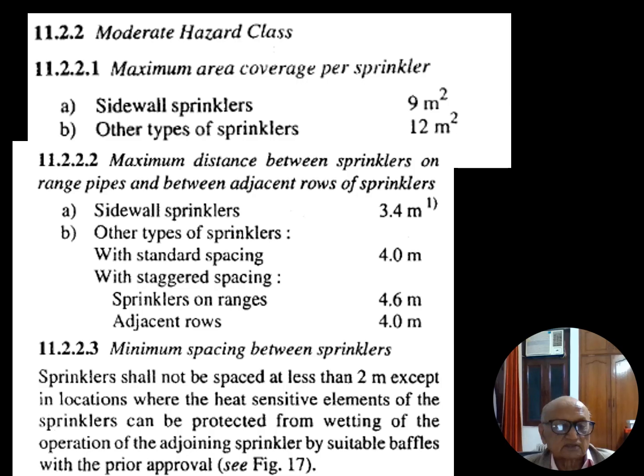Minimum spacing between sprinklers: sprinklers shall not be provided at less than 2 meter, except in locations where the heat sensitive element of the sprinkler can be protected from wetting by the operation of the adjoining sprinkler by suitable baffles, with prior approval. You can see figure 17 of National Building Code Part 4.